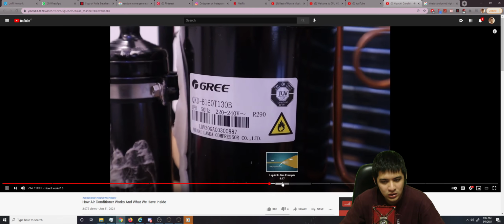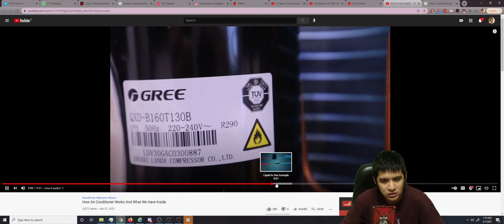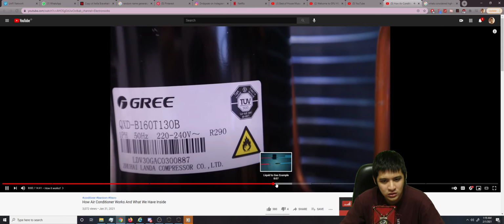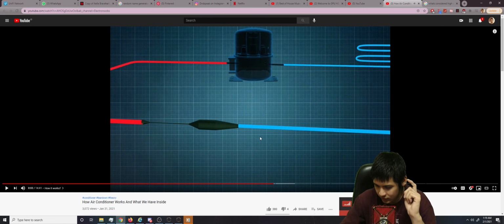And as you can see, my model is using the R290. And by the way, this is a very contaminating product that is damaging the ozone layer a lot. Okay, no. Some refrigerants did destroy ozone and have high GWP, like 410A has high GWP, while R22 has high ODP, which is ozone depletion potential. But I believe R290 doesn't do that.